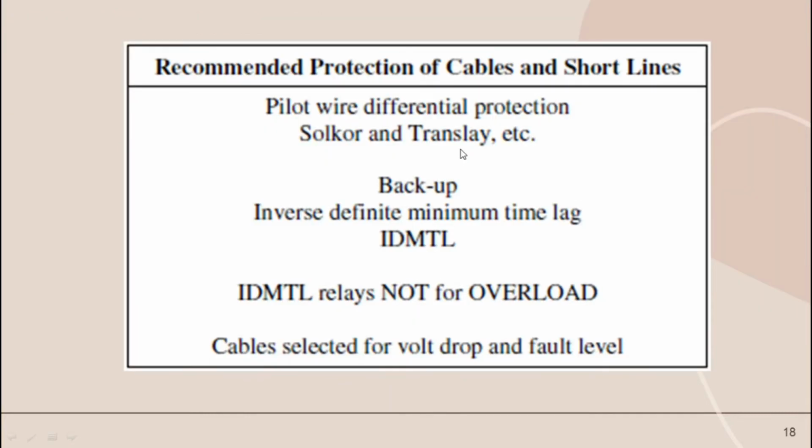Recommended protection of cables and short lines: pilot wire differential protection, Solkor and Translay, etc. Backup: inverse definite minimum time lag, or IDMTL. IDMTL relays not for overload. Cable selected for volt drop and fault level.